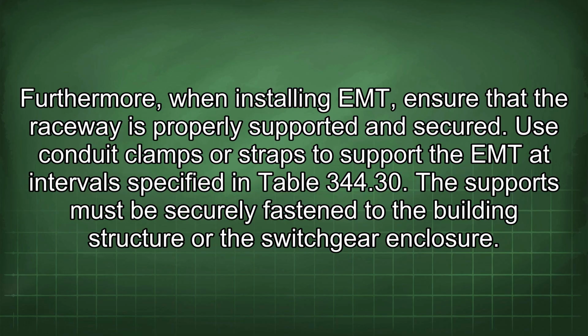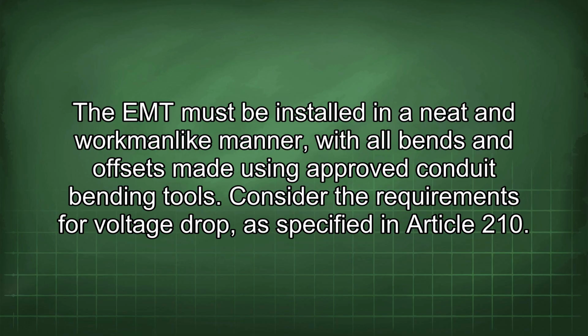Furthermore, when installing EMT, ensure that the raceway is properly supported and secured. Use conduit clamps or straps to support the EMT at intervals specified in Table 344.30. The support must be securely fastened to the building structure or the switchgear enclosure. The EMT must be installed in a neat and workmanlike manner, with all bends and offsets made using approved conduit bending tools.